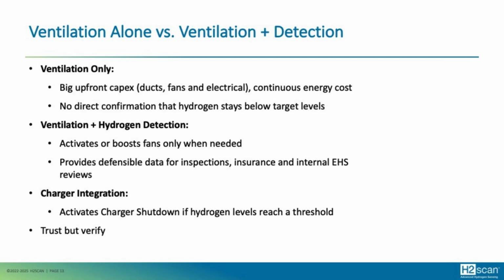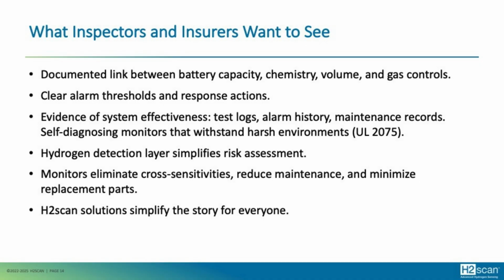But what do inspectors want to see on site? They want to see documentation. Pretty much all safety standards, model codes, adopted codes, basically all say the same thing. They want you to operate in a safe range. They want you to prove that you have a mitigation plan for controlling hydrogen or any kind of safety risk. And they want to know what your action's going to be when an alarm goes off, and make sure that you're taking an appropriate response, or the system is doing an automatic response, either way. And so test logs and alarm history, maintenance records, all these are basically required to keep on site in case the authority having jurisdiction would like to inspect those.